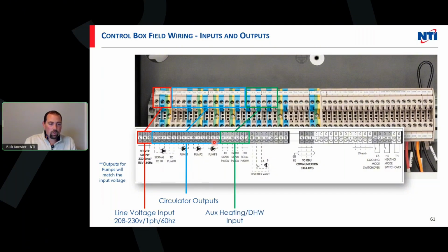The next 3 next to it are going to be our auxiliary heating terminals. So we have what we call our auxiliary heat, which basically works for both heating and hot water. And then we have our hot water tank backup heat and heating backup heat. So we have the ability to control the indirect backup or the buffer tank backup separately. And then we can have both of them energized off of the air handler.